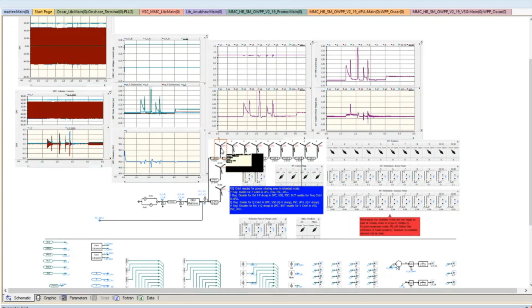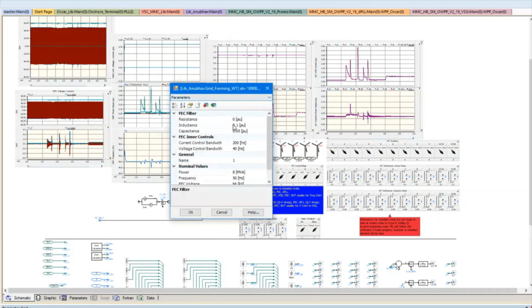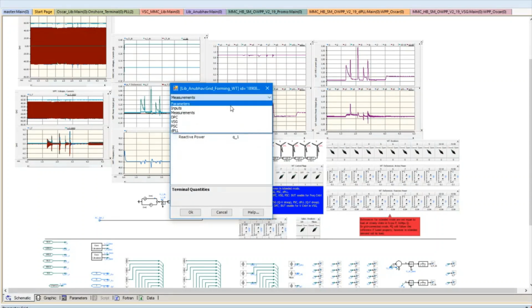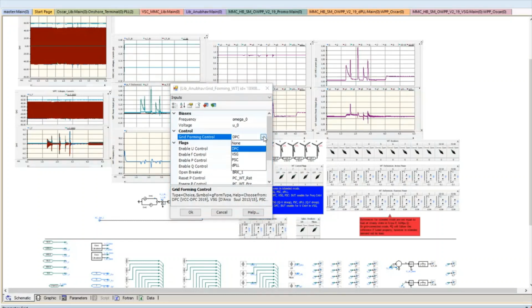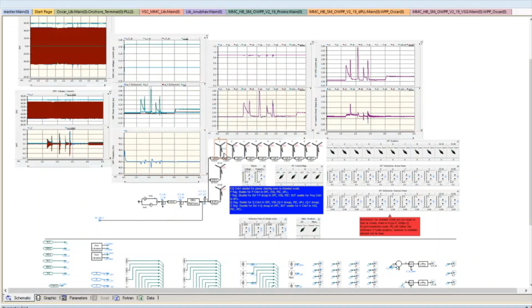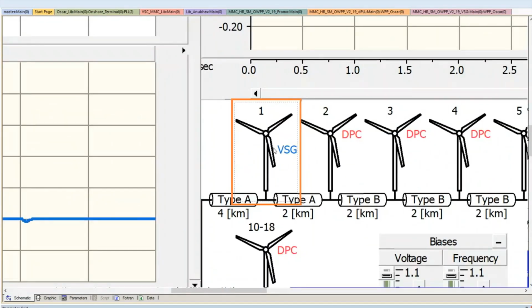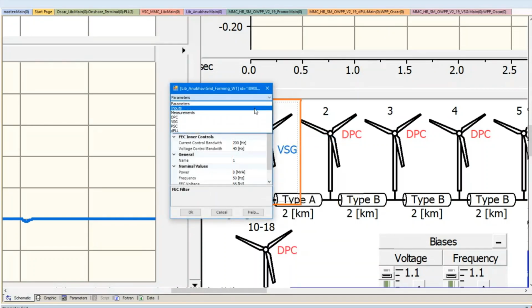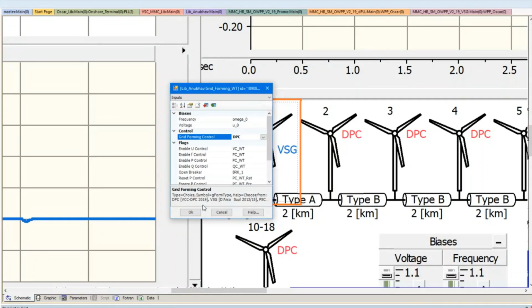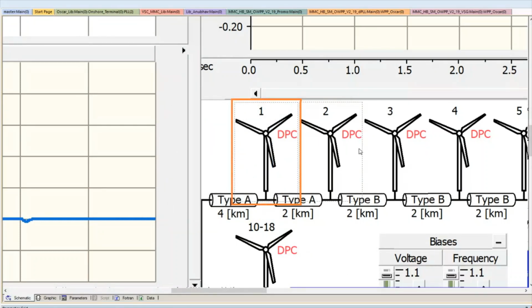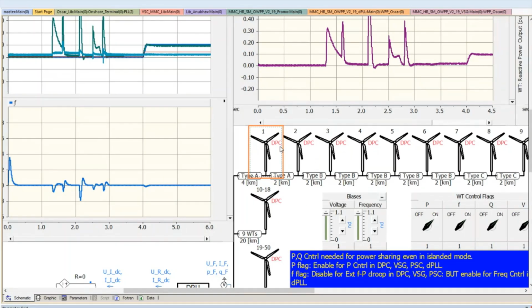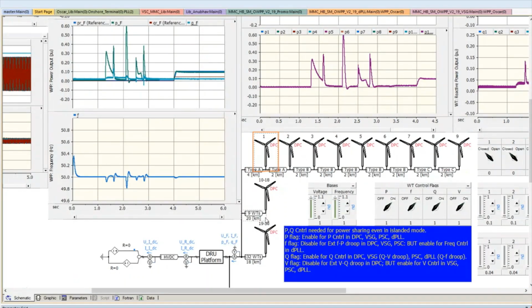All the controls are implemented in this one model. So after entering the values of the resistances and the filters, you can enter in the input what grid forming control you would like to use, and this indicator shows what grid forming control is being used right now by the wind turbine. Many studies can be performed with a mix of different wind turbine controls, choosing some wind turbines as grid forming and some as grid following. However, right now we choose the entire wind farm as grid forming as a whole.